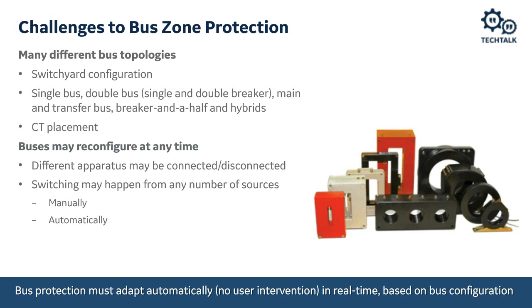Challenges to bus zone protection: An effective bus zone protection scheme should have flexibility to be applied at many different configurations due to the various bus topologies used. We'll discuss typical topologies and CT placements for bus zone protection. For example, there might be only one bus coupler CT, or for live tank breakers there might be a dead zone due to CT placement. In North America most installations are dead tanks, so this is less of an issue. Bus reconfiguration also provides challenges that our chosen bus protection scheme must handle.